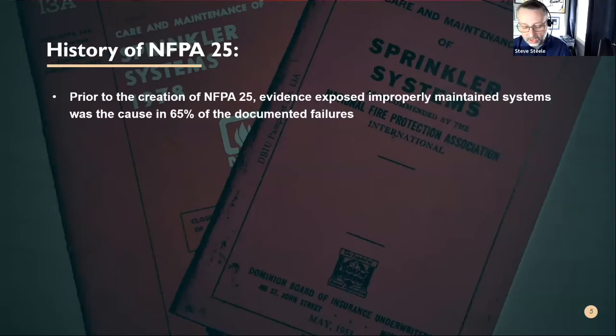So a lot of those causes were obstructions in the pipe, because it wasn't cared for or maintained or inspected. And also, if that valve was inadvertently left closed or not fully open, there would be a change in water availability and so forth. That was the major cause from what they found. So 65% of those documented failures came down to improperly maintained systems, something that could have been very easily picked up on a routine inspection or the annual test of that system by comparing results to previous years.